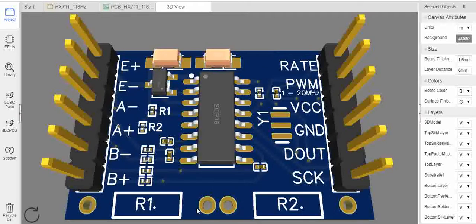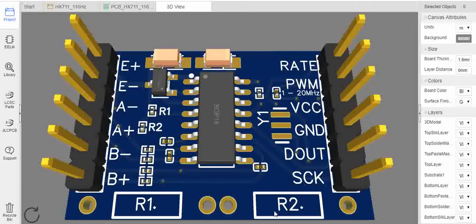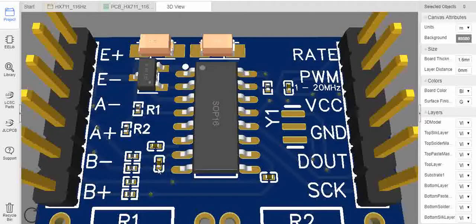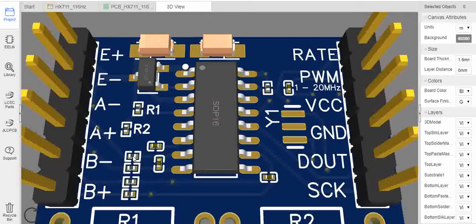These can also be used for fine-tuning as well. If you want to put high values in here to get a more precise voltage out here, if you want to set it to a precise value. Or as I said, you can get rid of these and just replace these two with whatever value you choose to set the excitation voltage. Here we have the capacitors on the two inputs and the 100 ohm resistors.